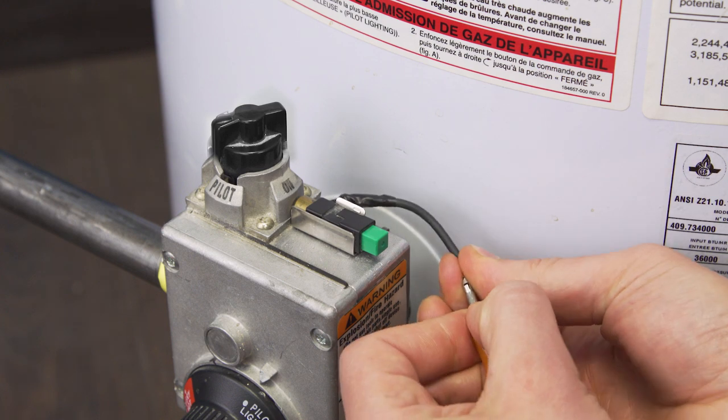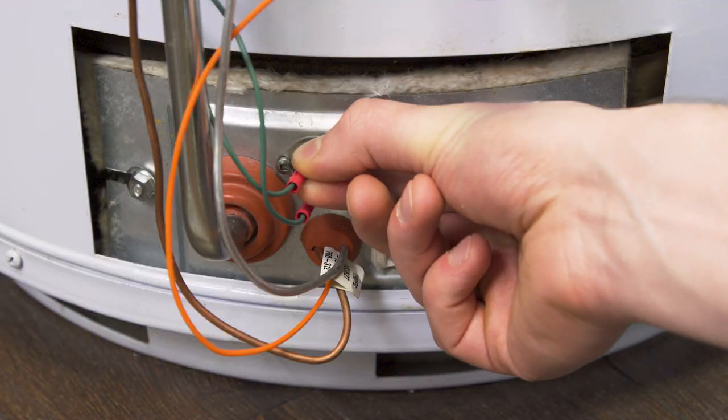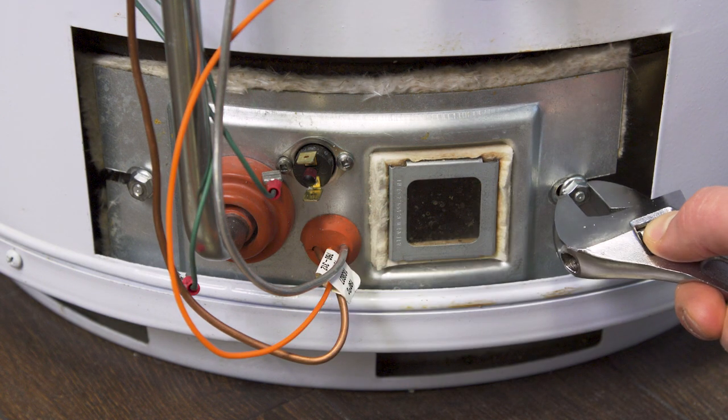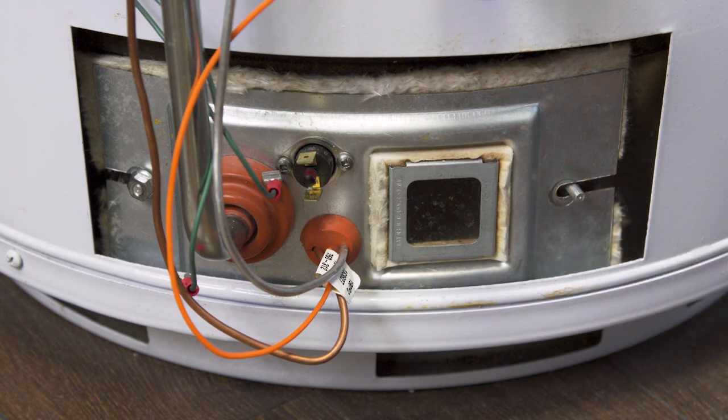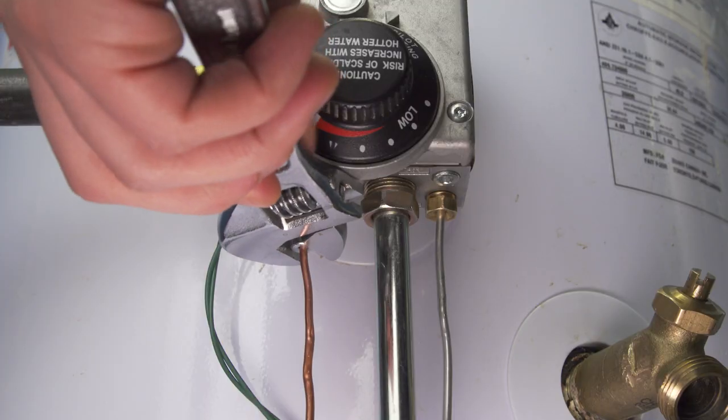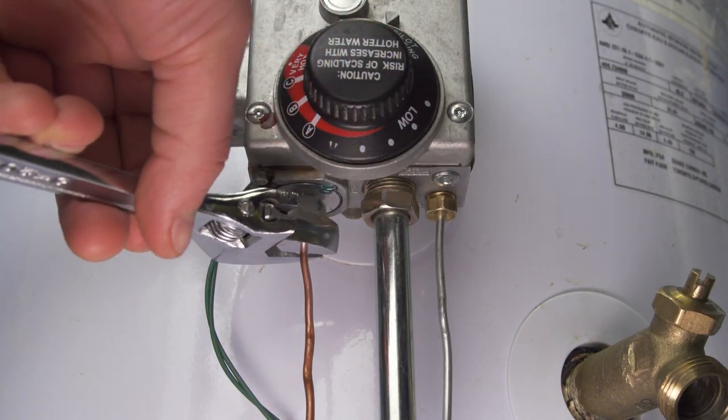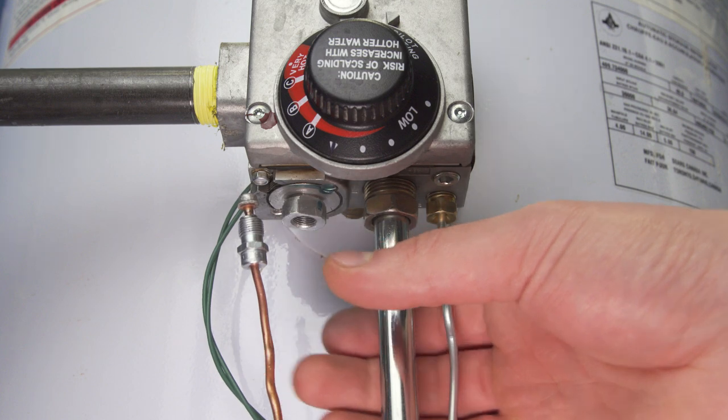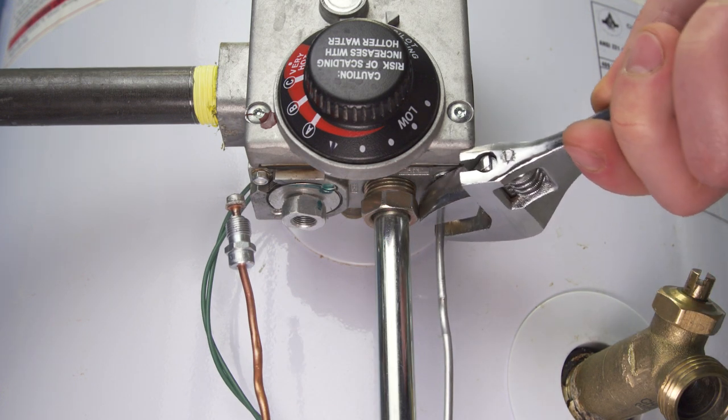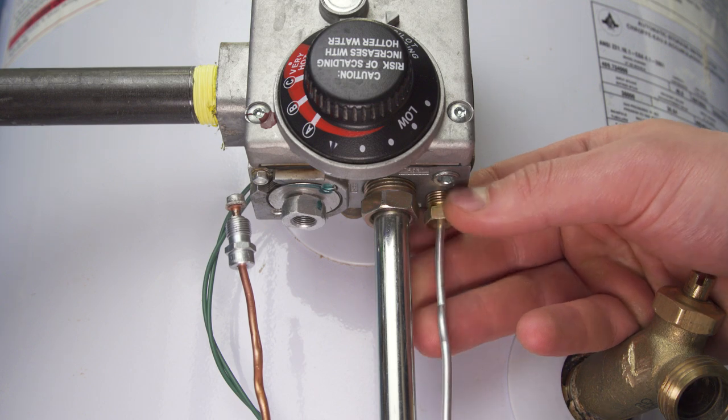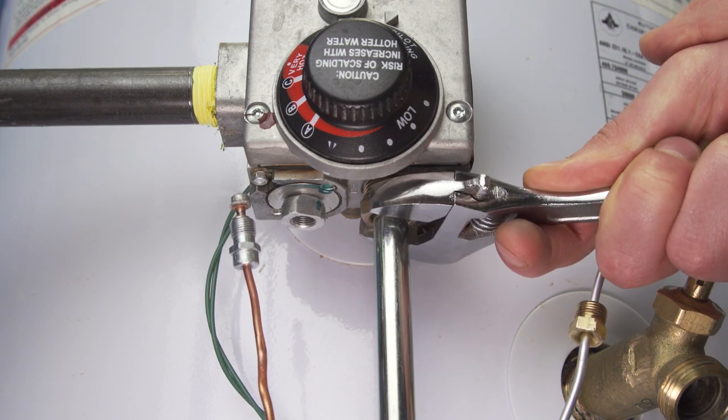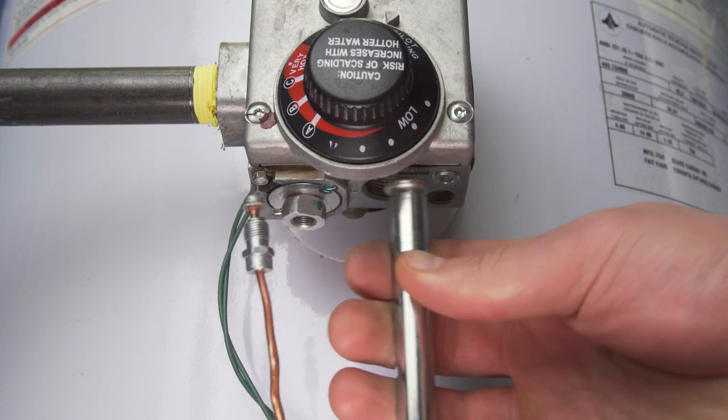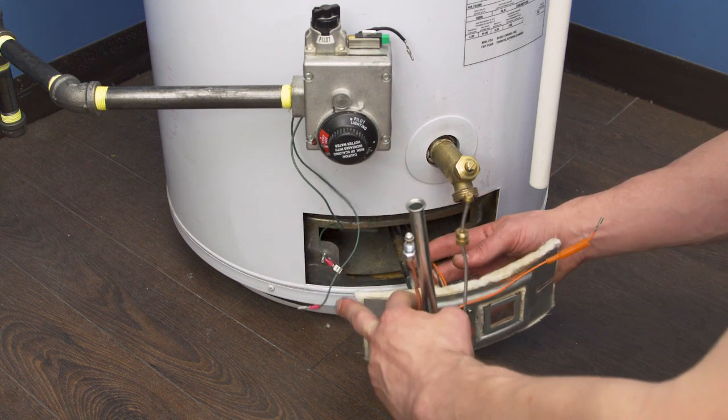Disconnect the igniter wire from the control valve. Next remove the wires from the thermal switch. Remove the two screws that hold the door in place. Use an adjustable wrench to unscrew the thermocouple. Next loosen and remove the pilot tube, but try not to bend or kink the metal. Unscrew and remove the manifold tube. Now slide out the whole burner assembly.